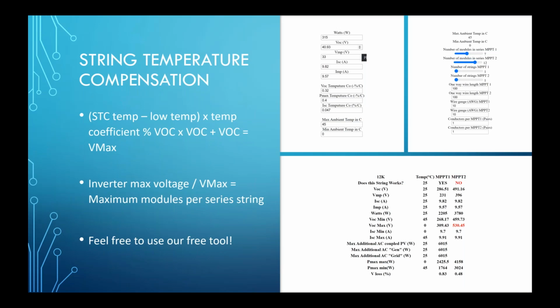What we watch for when you're stringing is voltage open circuit, temperature corrected. What you want to do is stay below 500. 500 VOC temperature corrected is the limit. At 550 VOC temperature corrected, damage will occur to the Sol-Ark. And really, we like it to be closer to, say, 450 would be the optimal spot to land on.